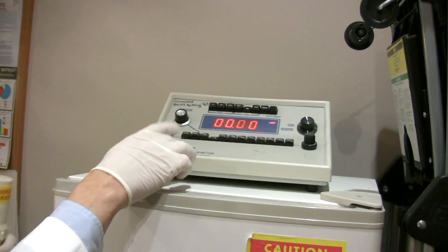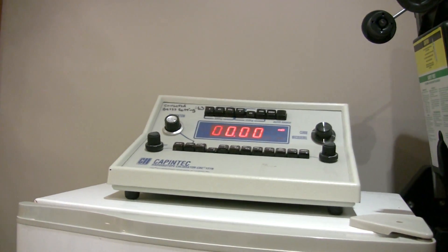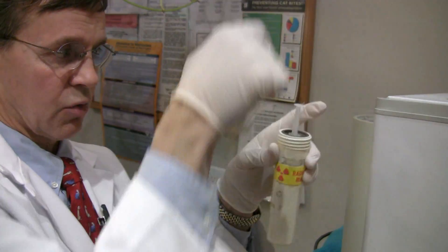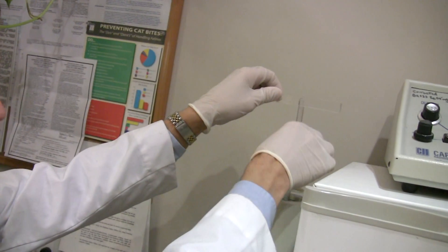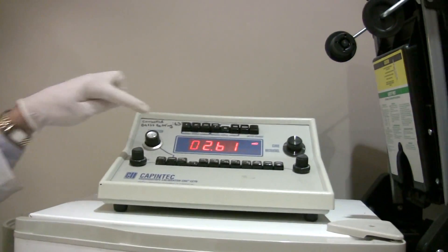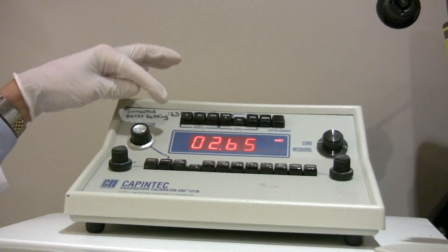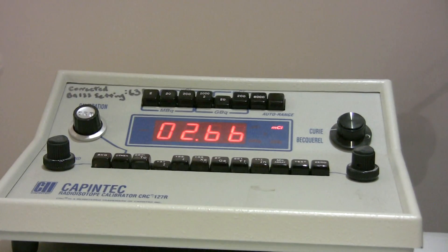With Petra, I've already measured the dose. We're giving a relatively low dose of about two and a half millicuries. You can see the dose calibrator here — we're measuring it. The doses come in a shielded container with the syringe, so we're going to take that syringe out and verify that it's the right dose. We put the dose into this counter and you can see it's reading 2.66 millicuries.